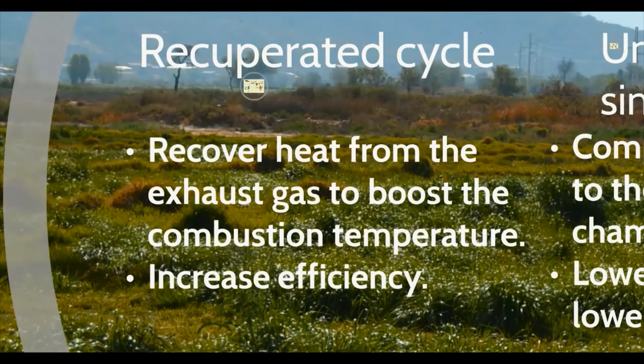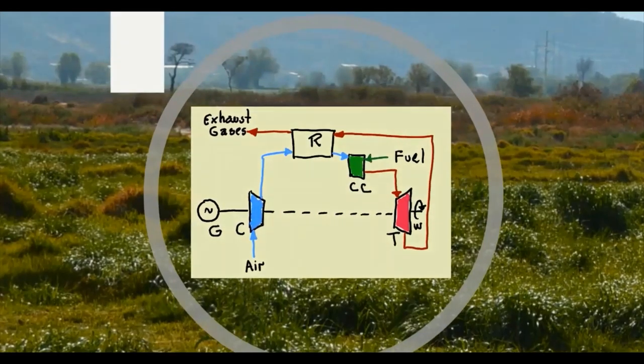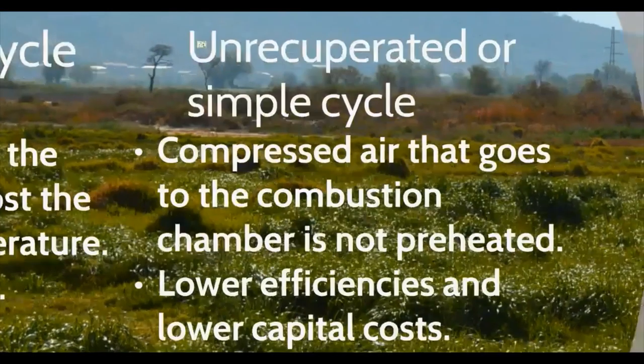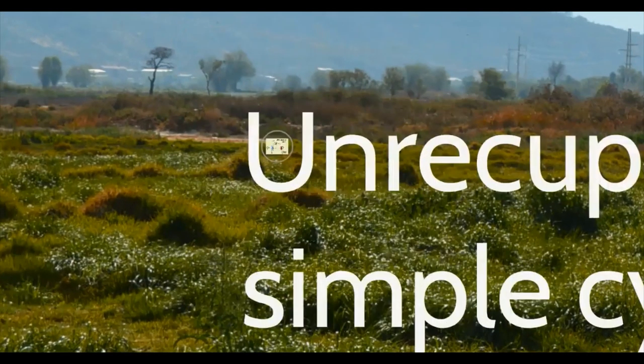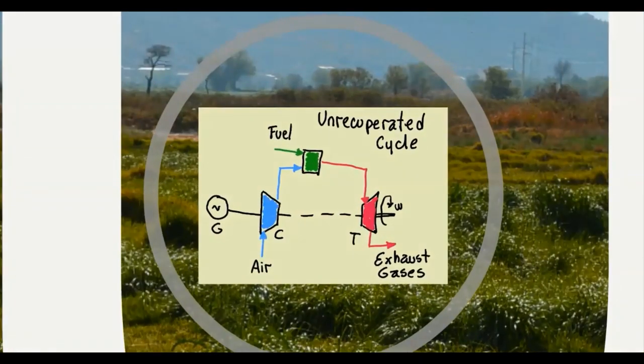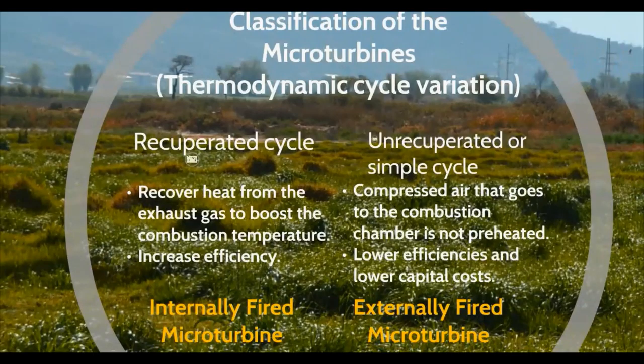Microturbines can also be distinguished by the variation in their thermodynamic cycle. There are recuperated cycle microturbines that recover heat from the exhaust gas to boost the temperature of combustion and increase the efficiency. In the case of the unrecuperated or simple cycle, it doesn't use the exhaust gas to preheat the compressed air. Therefore, it has lower electric efficiency, but also requires lower capital costs than the recuperated cycle microturbines.